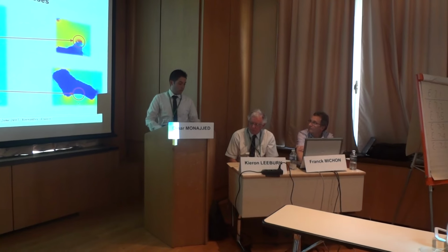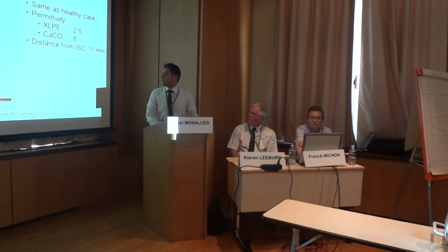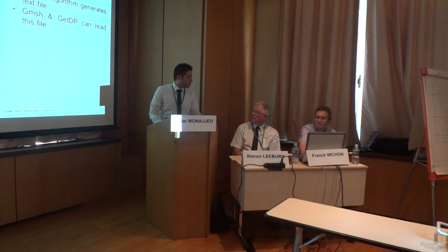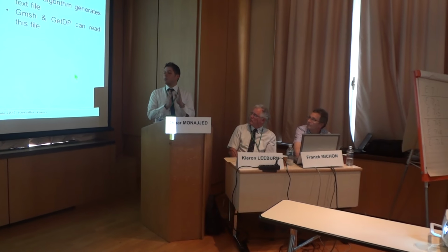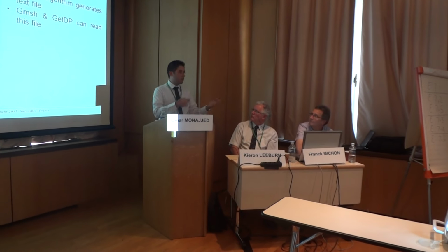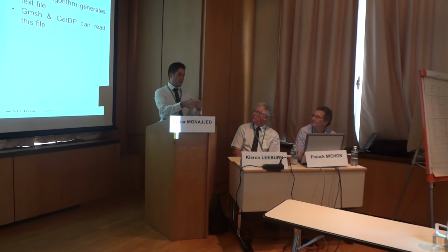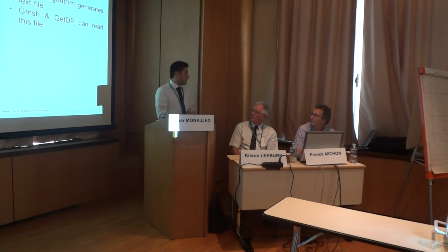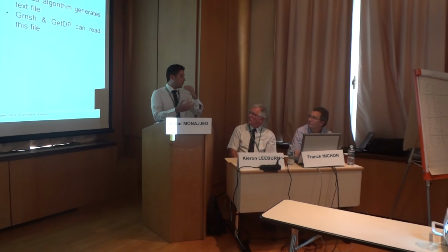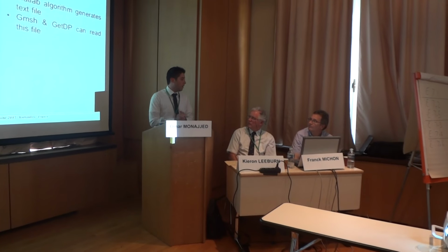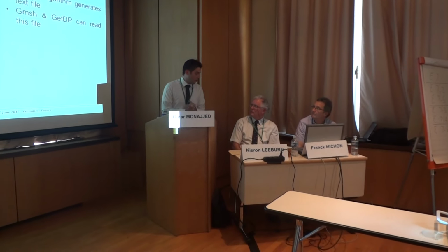Yes, yes. What we have done here is almost like a software, because if you have different impurities and different materials, you only have to input the image of the impurity, the permittivities of the material, and the distance from the inner semicon to this one. And then you will have the stresses directly.